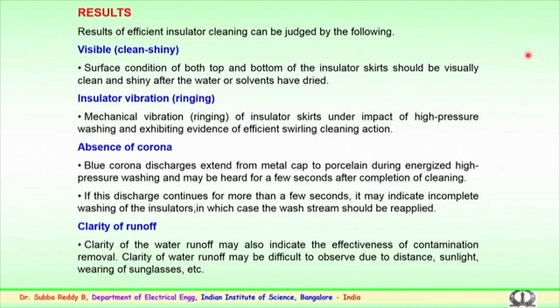Care has to be taken to check whether some residue is left on the surface after cleaning. If the surface is not clear and you can spot patches on the insulator surface, this is not proper cleaning. Proper cleaning has to be done so that the insulator, after drying, looks visibly clean, and in case of a ceramic insulator, the glaze shows a shiny appearance. This has to be observed.